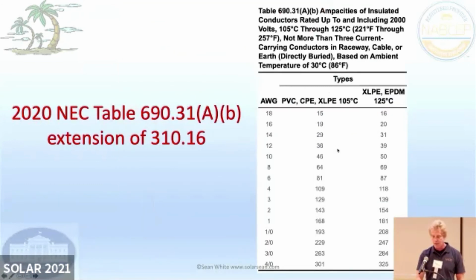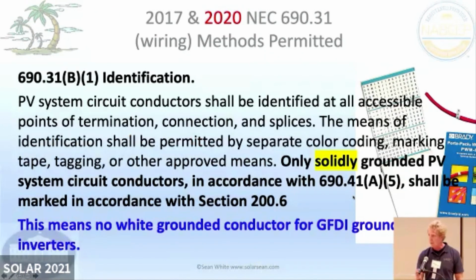Here are the ampacities of these wires. And we'll see if people start using that. That would just mean you could use a really skinny wire, which I don't see anybody really using. There's special rules for marking things. So circuits need to be marked with these PV systems so you don't get mixed up between one side of the conduit and the other.